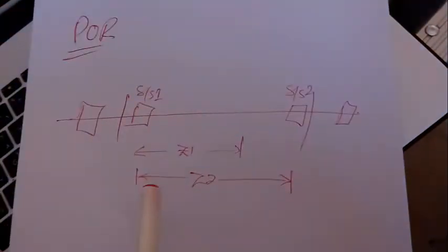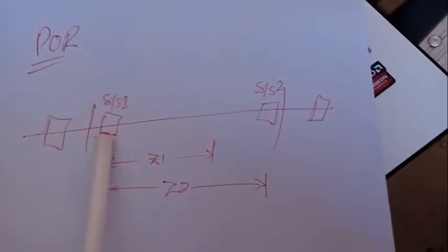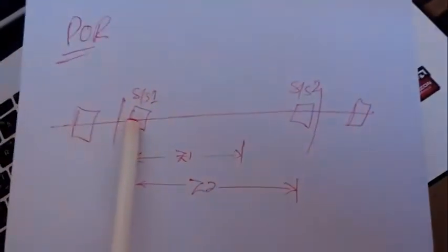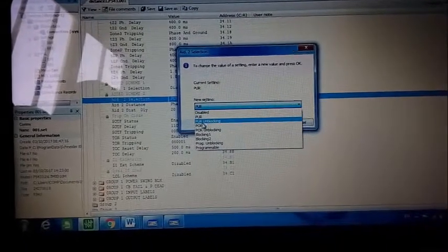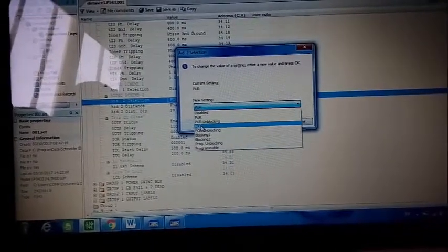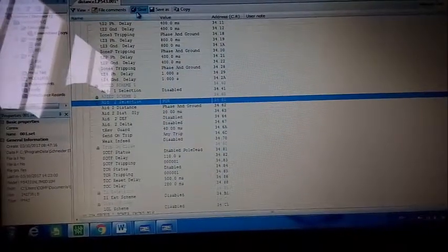The next scheme is the Permissive Overreach scheme. In this scheme, if the fault is in zone one or zone two, it will send a carrier receive signal to the other substation to make a trip. We go to settings, enable the Permissive Overreach scheme, and save.